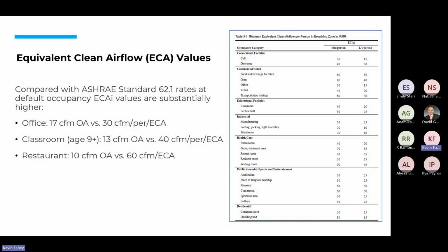So I think we're all aware that if you tried to do that with outdoor air, the cost of conditioning that outdoor air to dilute would be incredibly costly. If you try to do it just with filtration, you're going to be putting in very high MERV rated filters, and it costs a lot of money to push air through those filters, and you may not have the capacity with your air handlers to even increase MERV ratings on filters.